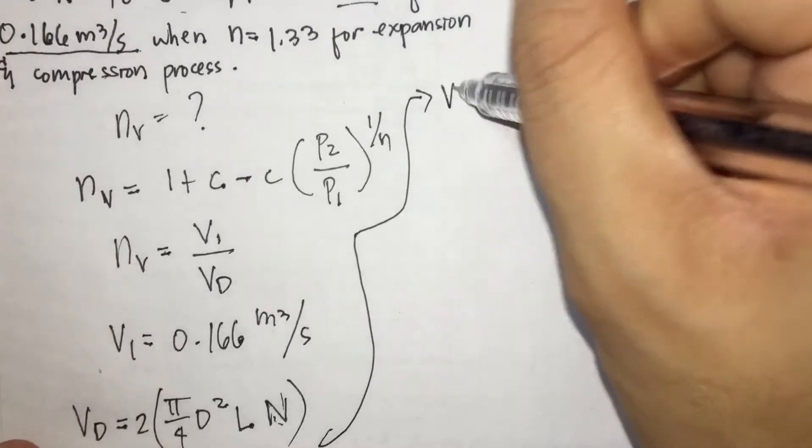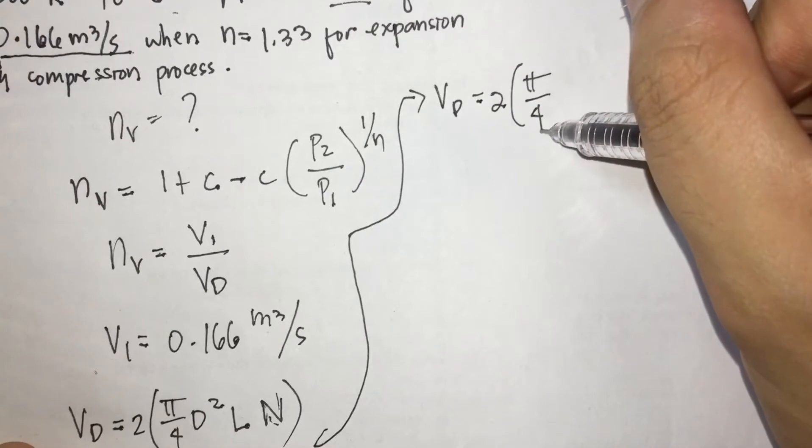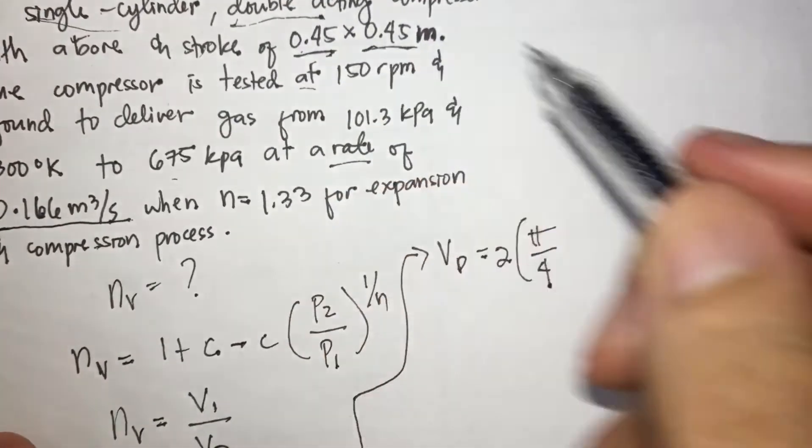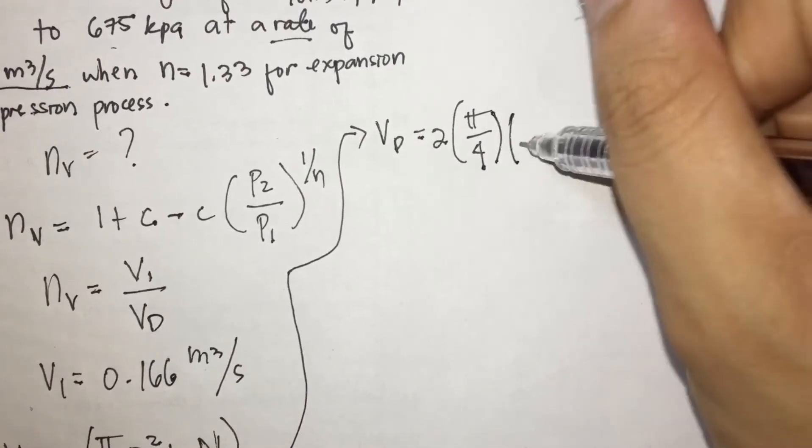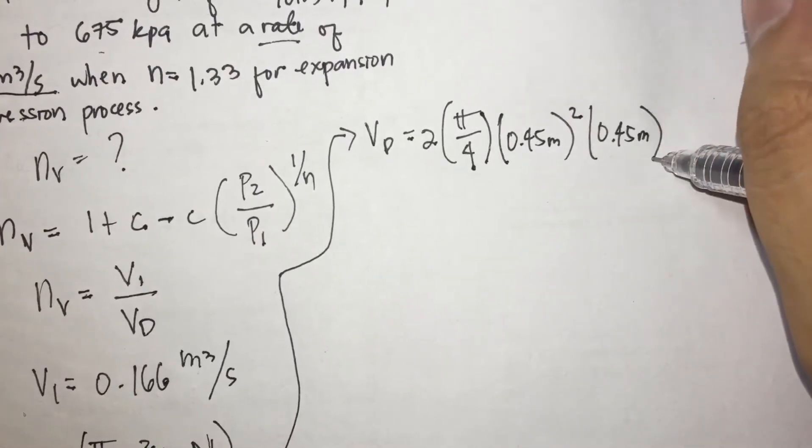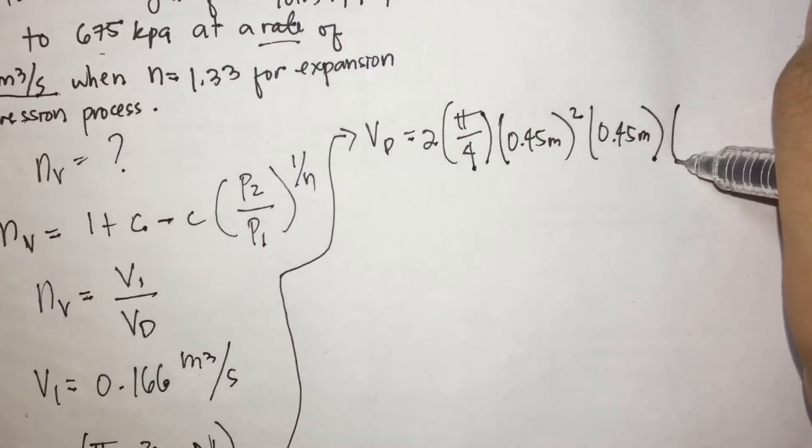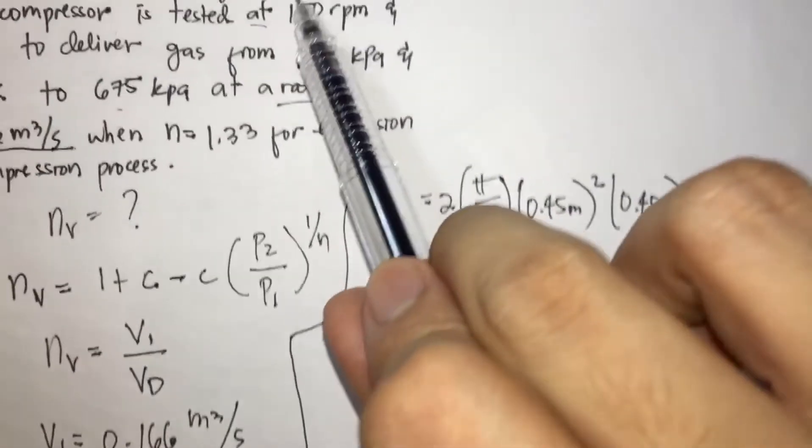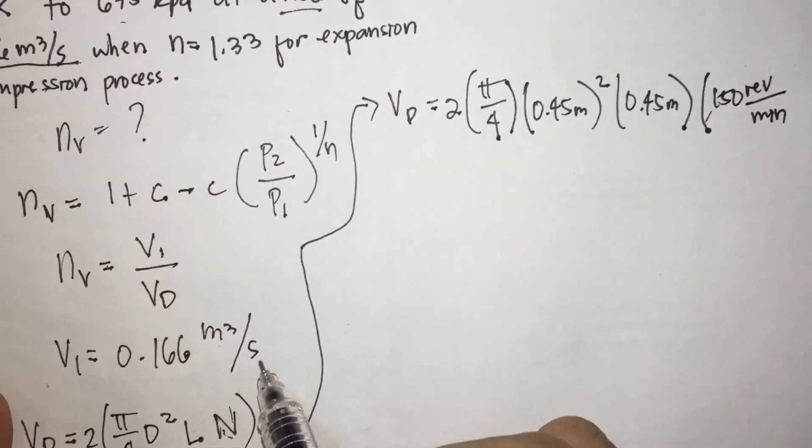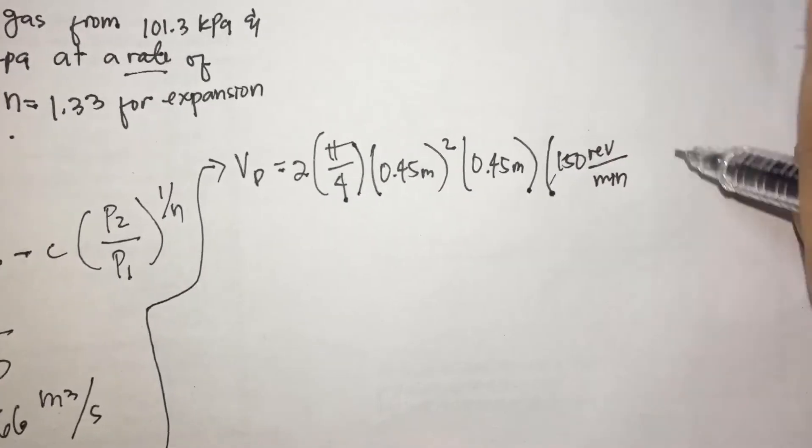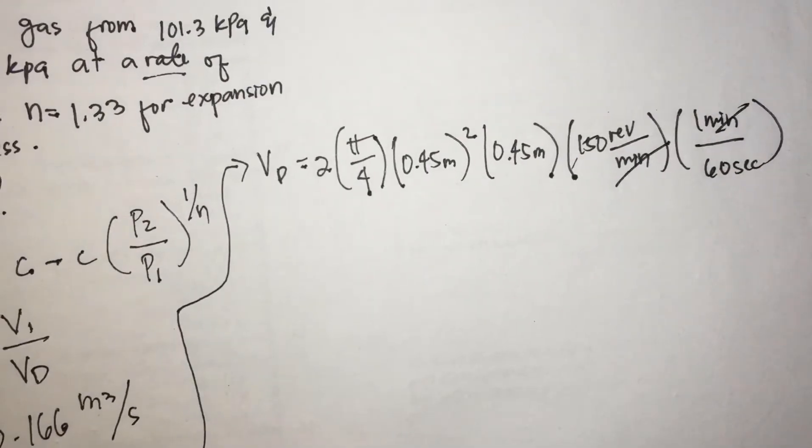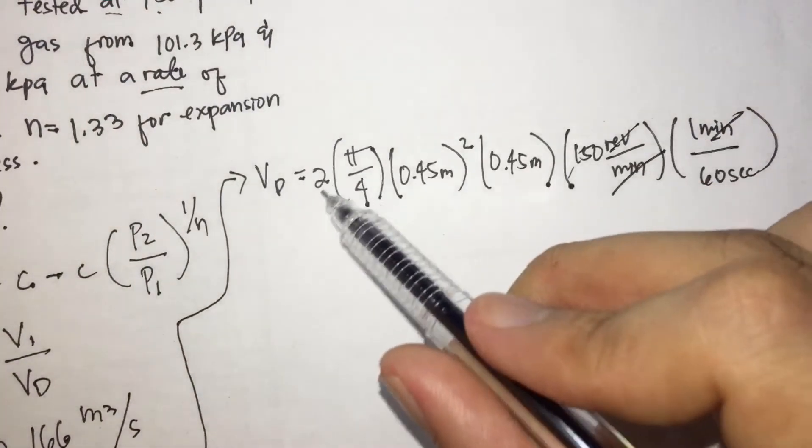So VD is equal to 2 times pi over 4, D diameter. Where's our diameter? Diameter and stroke are both 0.45 meter, so it's in meters. Times 0.45 meter squared times 0.45 meter, and N speed, tested at 150 rpm, 150 revolution per minute. Since our V1 is in seconds, we should make VD in seconds too, times 1 minute is 60 seconds.